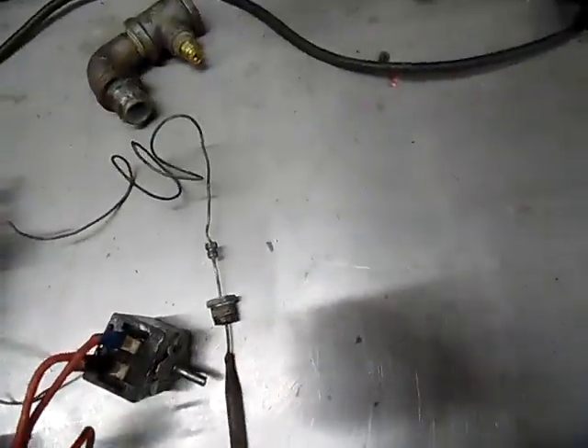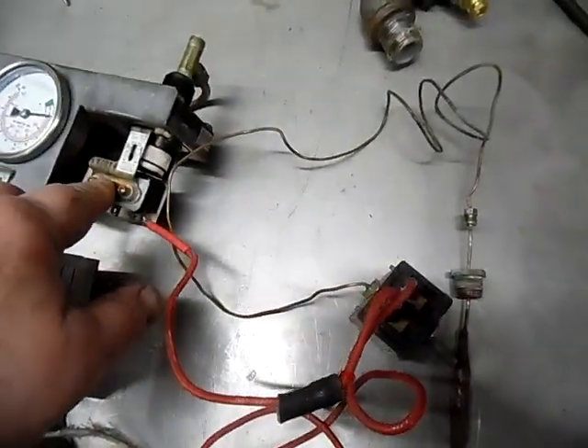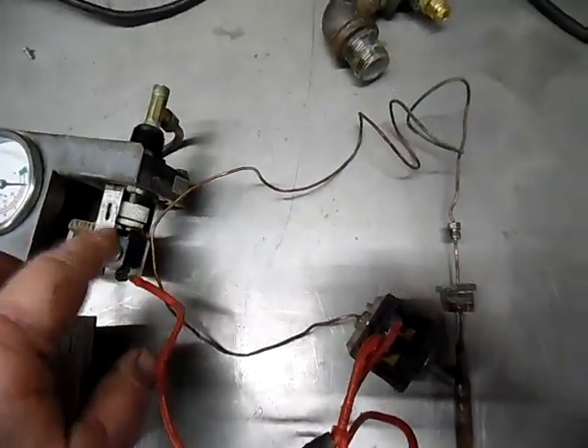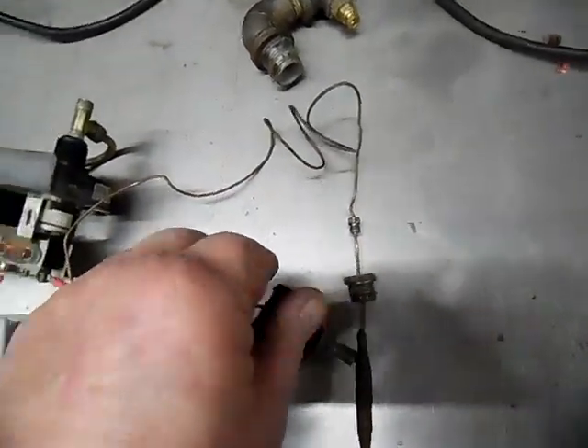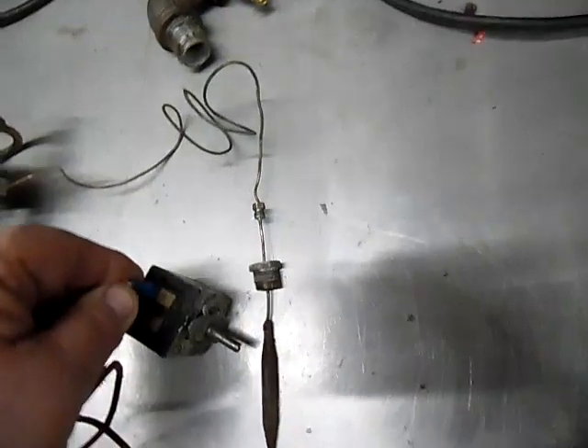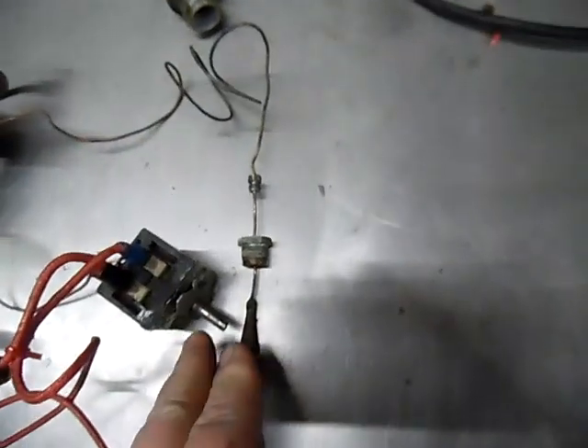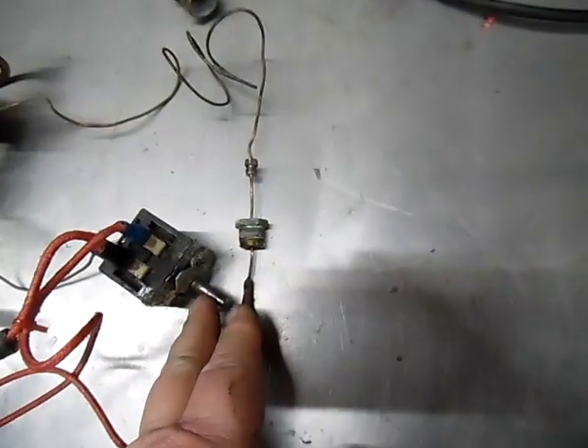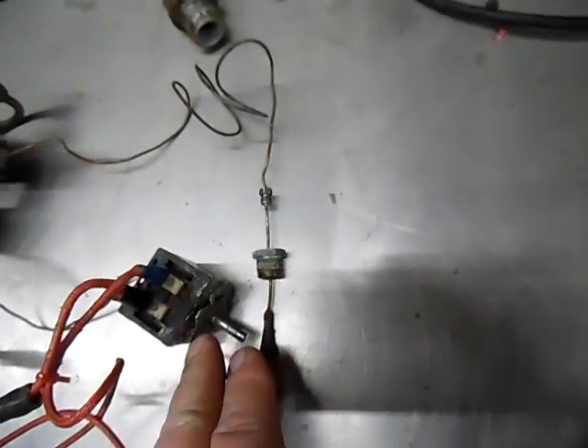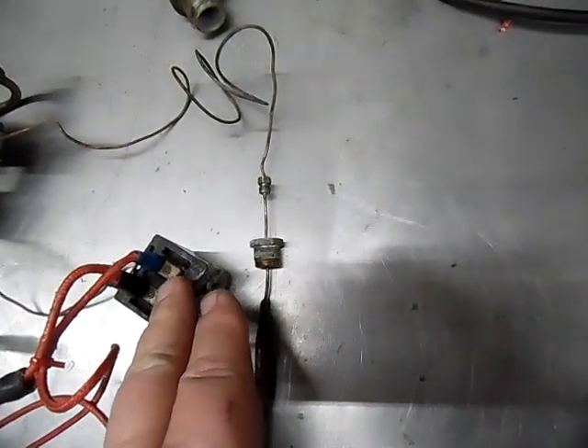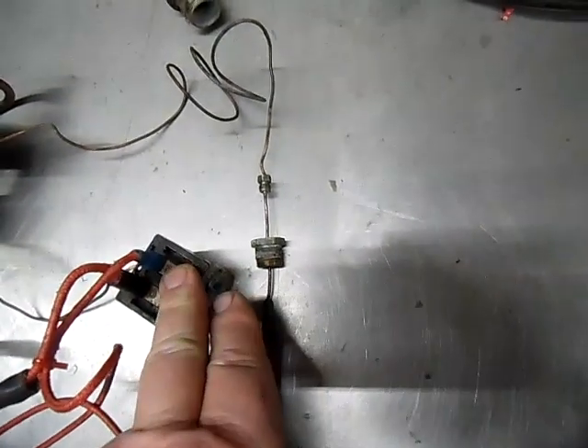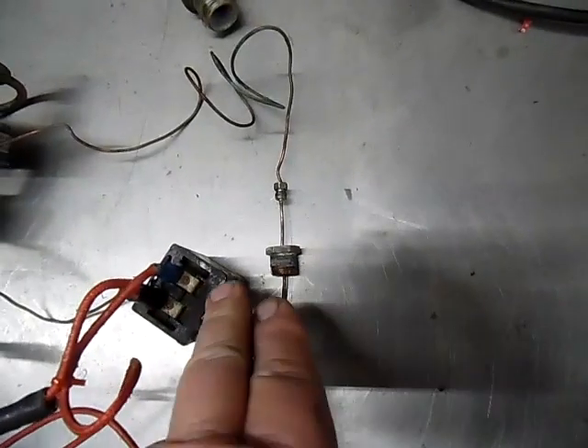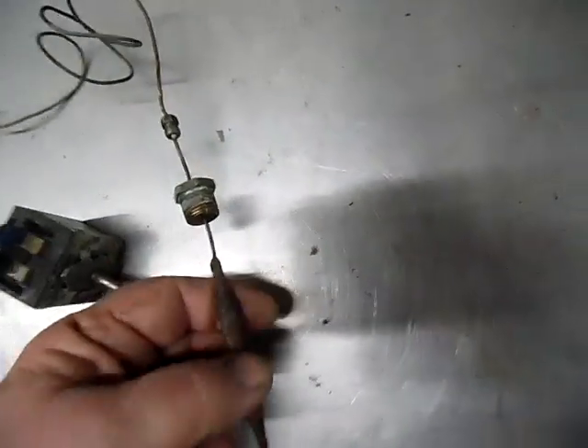But if you have voltage here and not here, then you're looking at your pressure switch. If you don't have it on this side of the pressure switch, check your connectors. Connectors are all good. Then you go to this. You can jiggle around with the up and down. This turns on at a low temperature. You can actually hear these thermostats click. Once they click from 100 on up, roughly to around 300 degrees, you will have continuity between this, and the bulb is what reads the temperature.